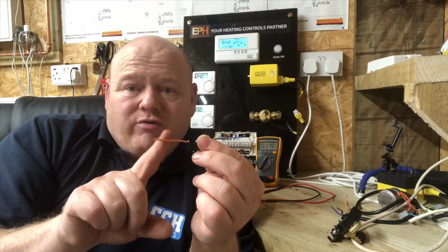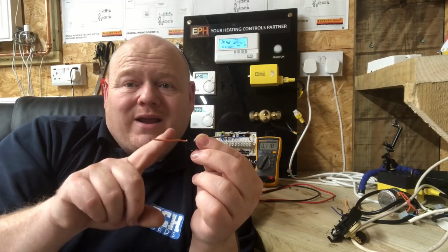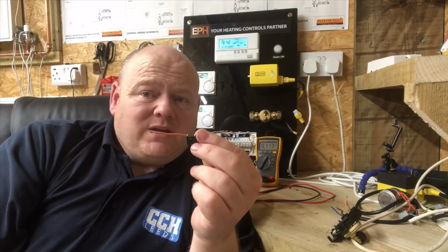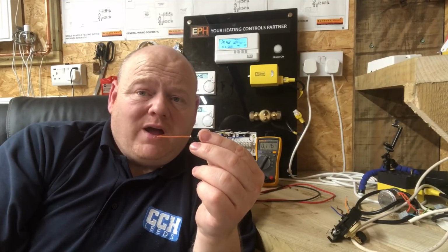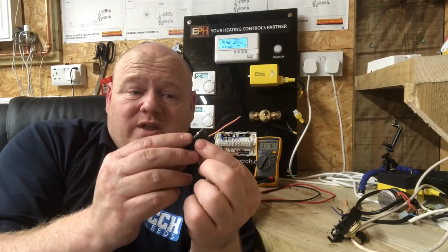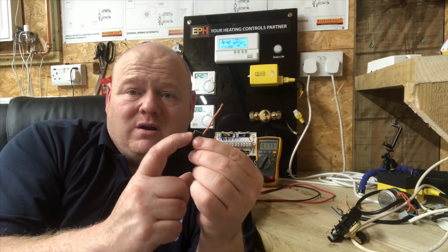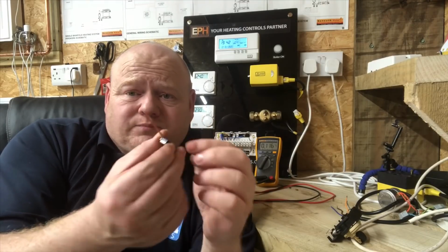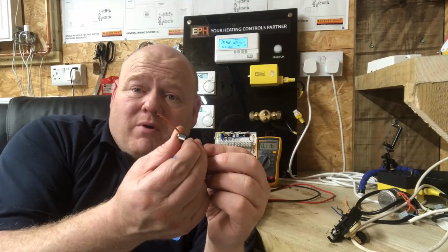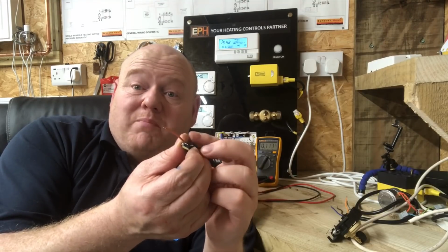So then this orange wire would go back and feed the boiler. There's a couple of things with this. Sometimes if you've got a fault and the boiler's constantly on, it could be that your micro switch in there is jammed. If that were jammed open, your clock could be turned off and your boiler could be on.